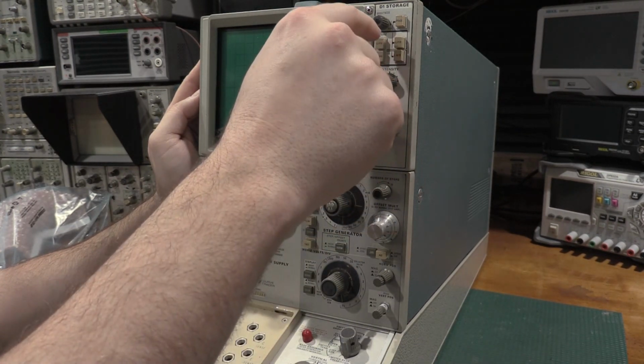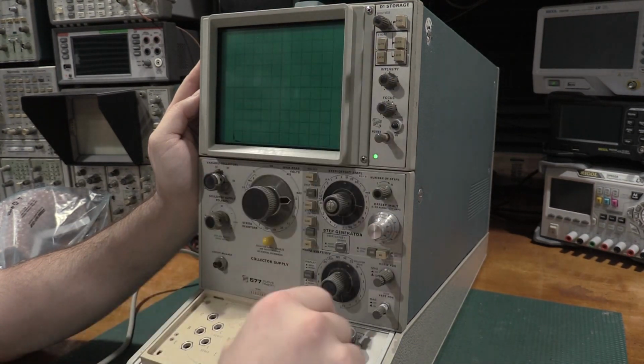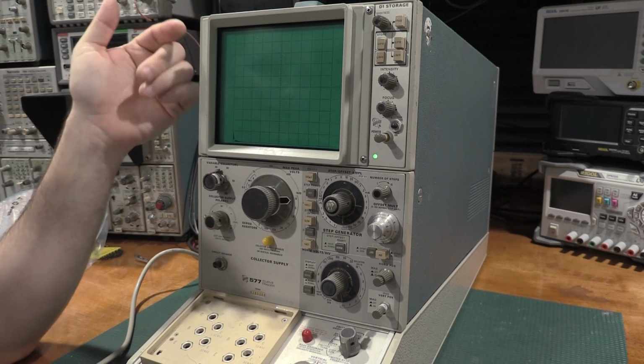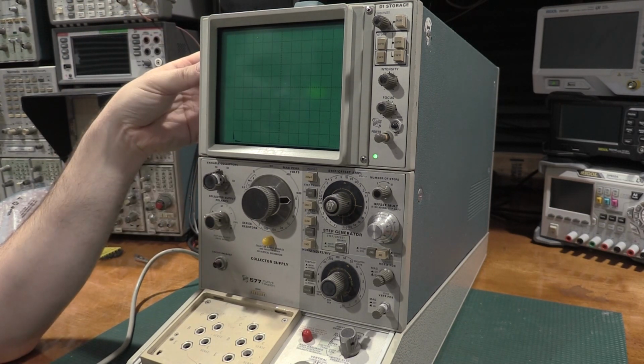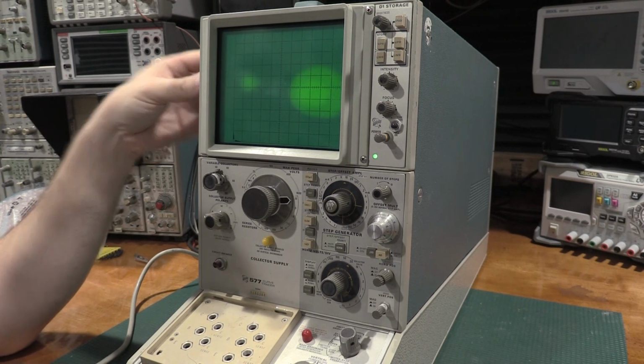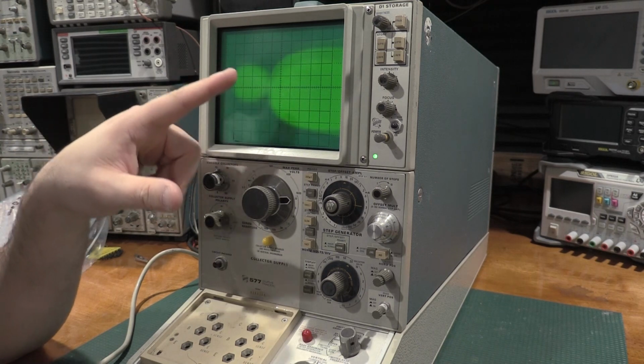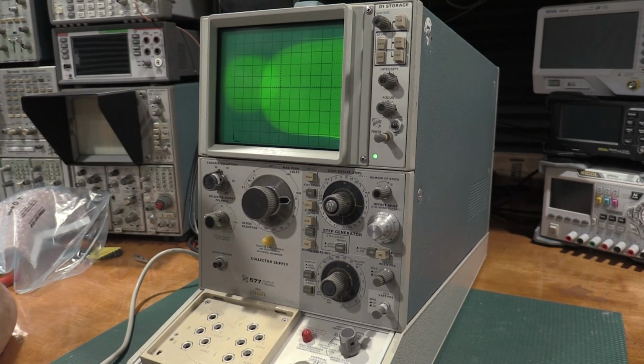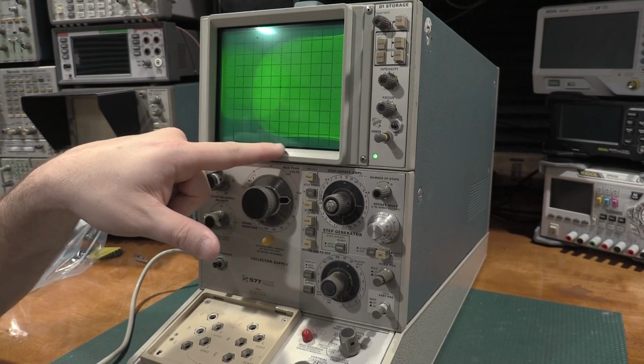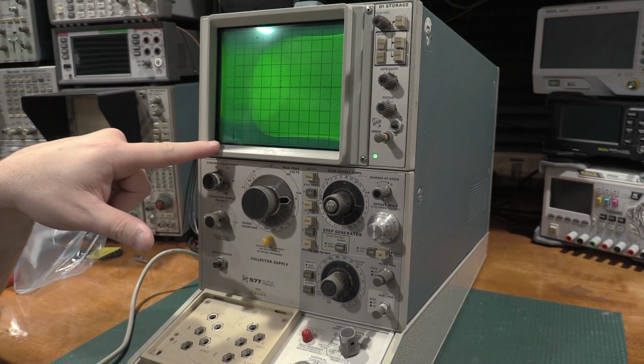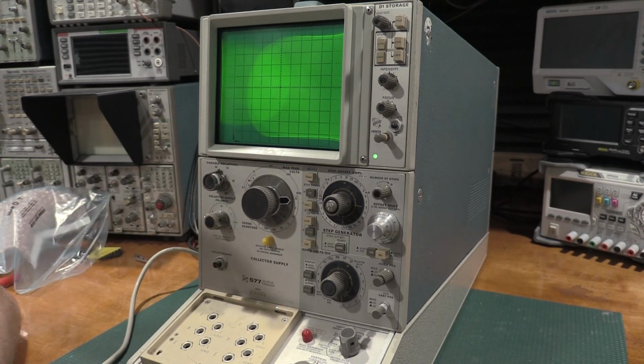Now, first thing you want to do, storage upper and lower, brightness all the way up. What that's going to do is put a lot of flood gun current in, and the manual says, if I remember correctly, to do this for 6 minutes if the tube has been off for a couple of days. You're going to see it kind of bloom in like this. This is the storage function coming back after a amount of storage. Now, what you'll see is it's not fully saturated the tube yet. This is going to expand over the time period as it warms up and bring the storage functionality back. If the unit hasn't been on, this procedure should be done, at least the manual calls out for it, for the storage function to function.